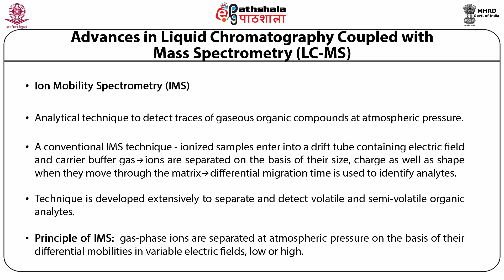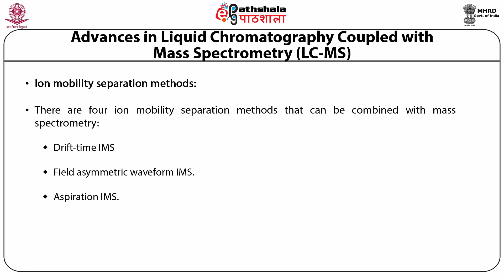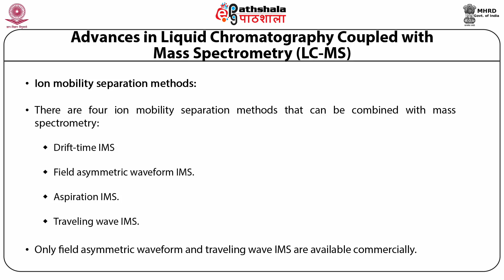In the last few decades, the IMS technique has been developed extensively to separate and detect volatile and semi-volatile organic analytes. The basic principle of IMS remains that gas phase ions are separated at atmospheric pressure on the basis of their differential mobilities in variable electric fields, low or high. Currently, there are 4 ion mobility separation methods that can be combined with mass spectrometry: drift time IMS, field asymmetric waveform IMS, aspiration IMS, and traveling wave IMS. Out of these, only field asymmetric waveform and traveling wave IMS are available commercially for coupling IMS with LC-MS.